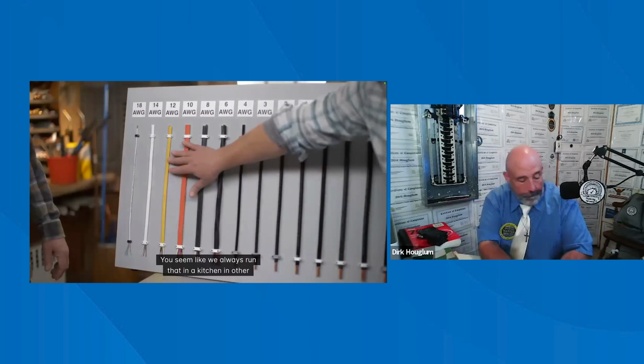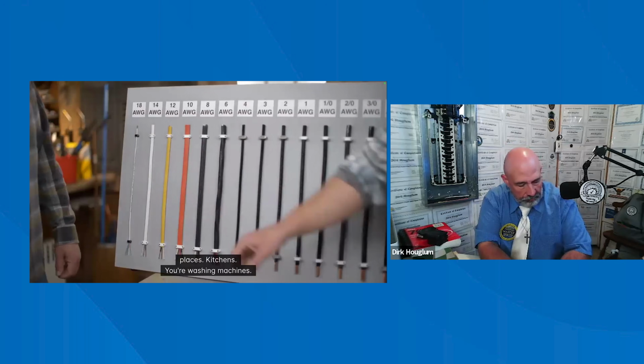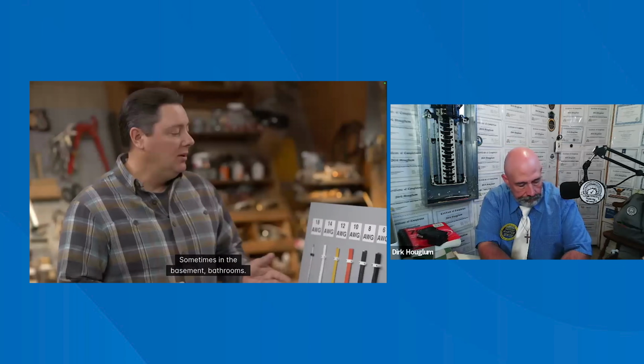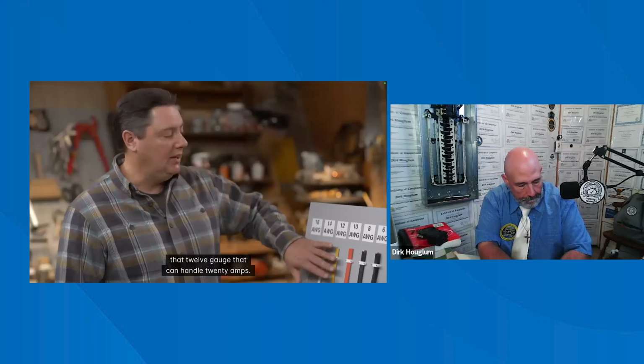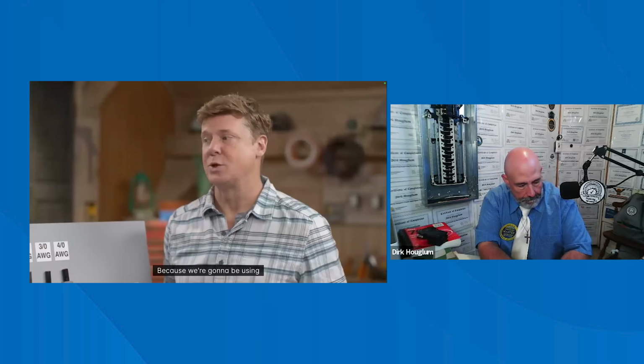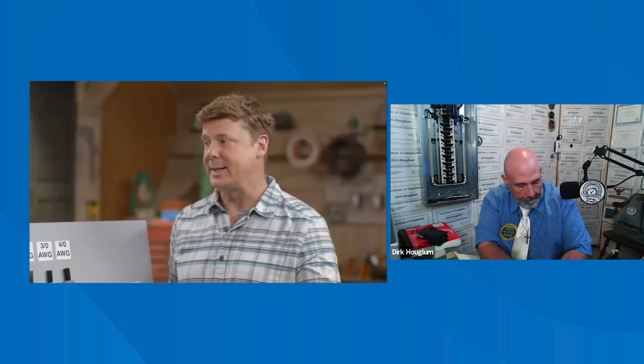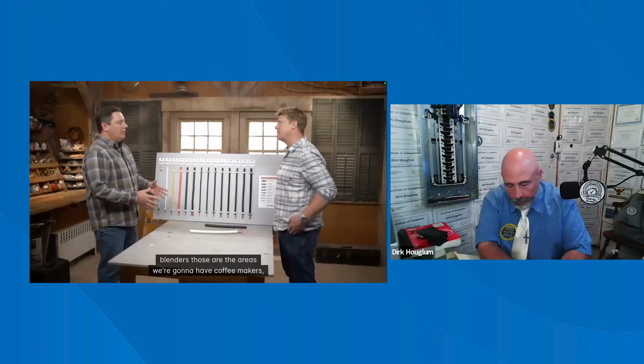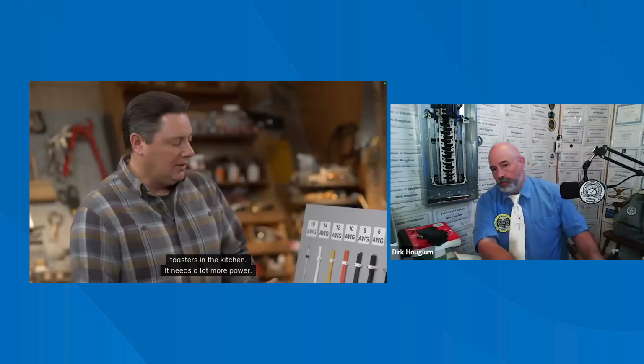Also familiar with this. You seem like we always run that in the kitchen and other places. Kitchens, your washing machines, sometimes in the basement, bathrooms. We want that larger size, that 12 gauge that can handle 20 amps. Because we're going to be using appliances that pull more electricity, a dishwasher, a blender. Exactly. So those are the areas where we're going to have coffee makers, toasters in the kitchen. Needs a lot more power. Want to have a larger cable that can handle that.